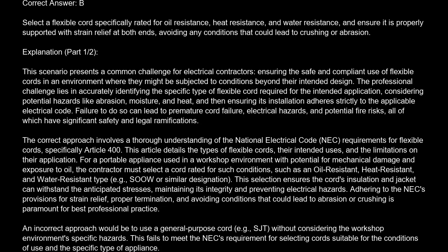The correct answer is B. Select a flexible cord specifically rated for oil resistance, heat resistance, and water resistance, and ensure it is properly supported with strain relief at both ends, avoiding any conditions that could lead to crushing or abrasion. Explanation. This scenario presents a common challenge for electrical contractors, ensuring the safe and compliant use of flexible cords in an environment where they might be subjected to conditions beyond their intended design.